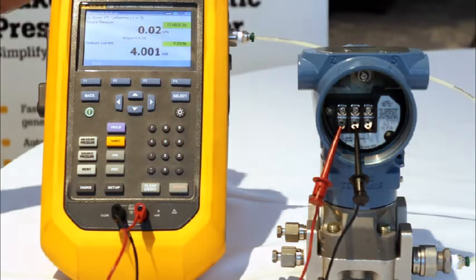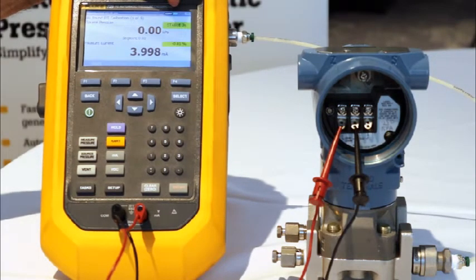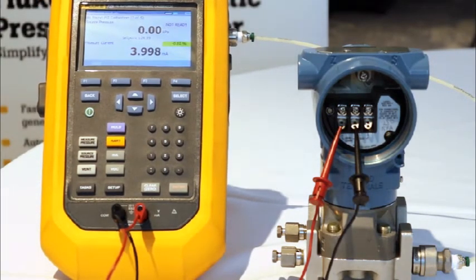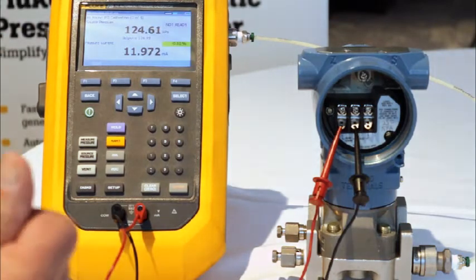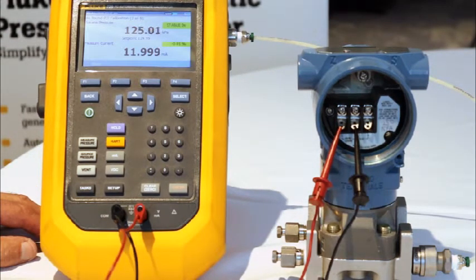Our first test point, 0 kPa, it'll be stable for 5 seconds, and then it'll jump to the next test point, which is 125 kPa. Calibrator will start pressuring up. You can hear the electric pump working. That's the coarse adjustment to get the pressure applied to the transmitter within range of the fine adjustment. Now the fine adjustment occurs with a group of pulse width modulated air valves that essentially do the fine tuning to dial in the pressure that we want to apply.